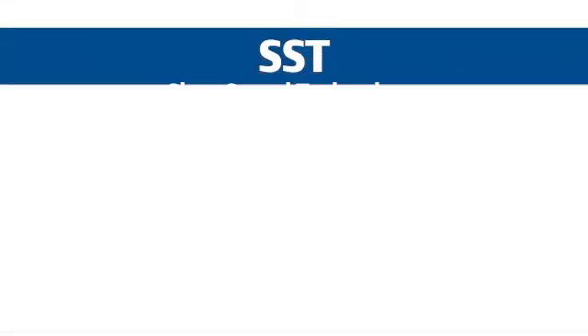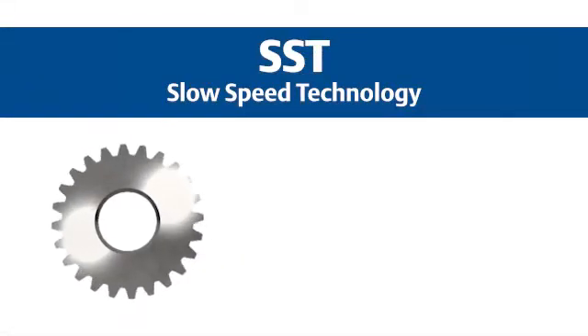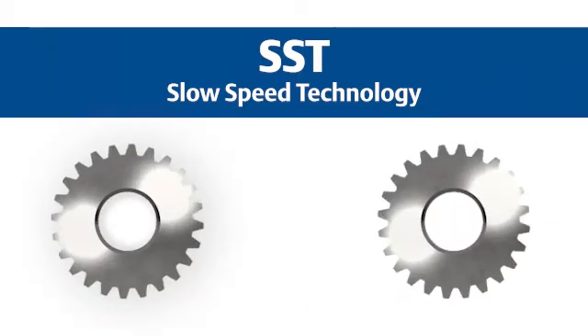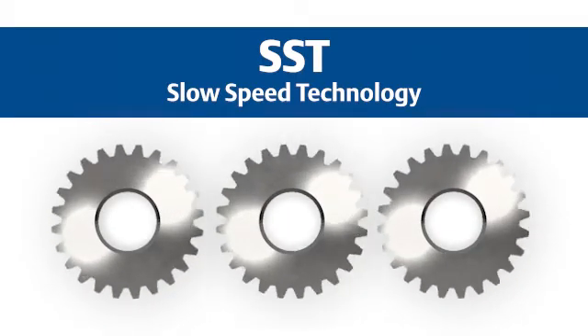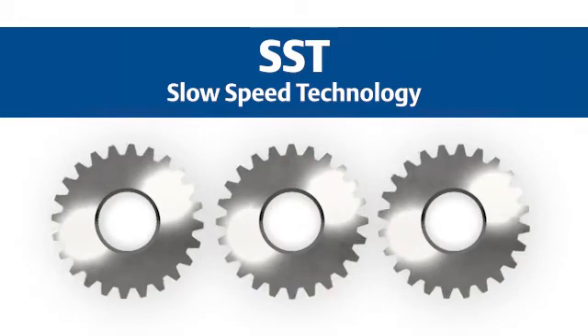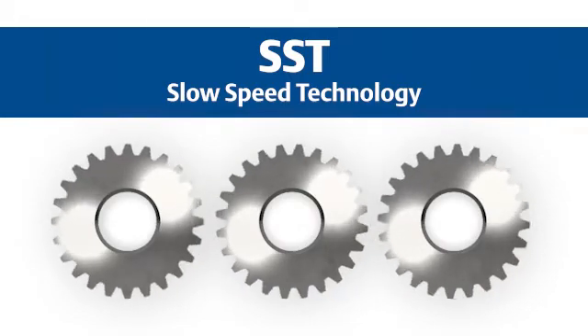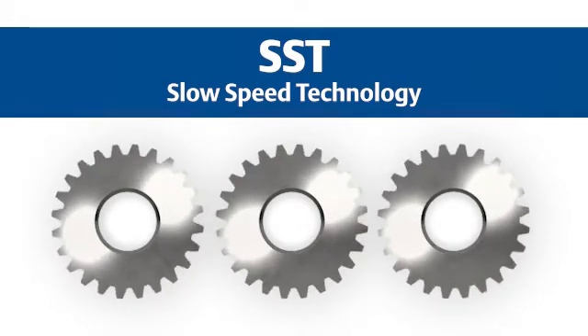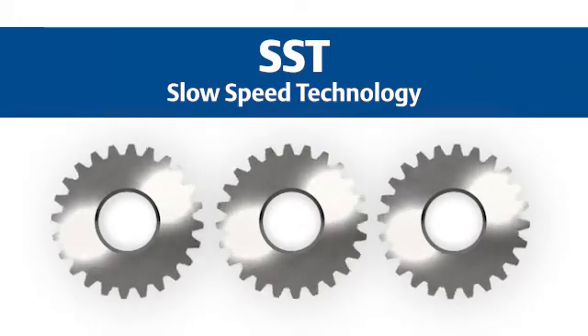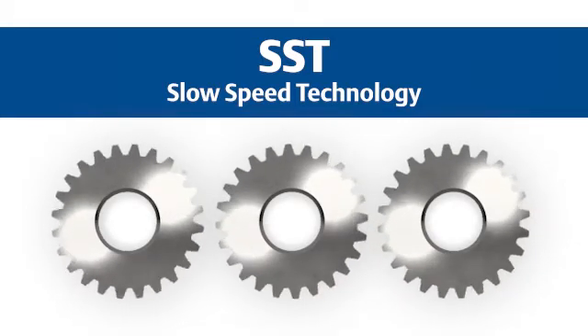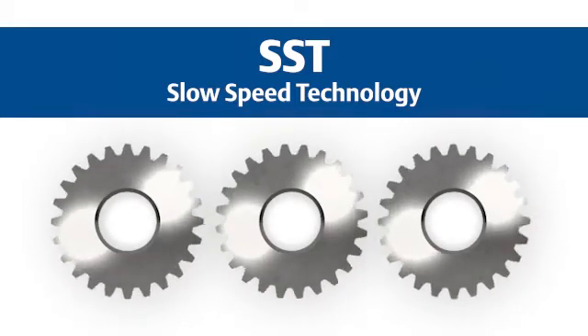Low-frequency analysis is sometimes referred to as SST or slow-speed technology. It applies to machines turning at very low speeds, typically below 10 Hz or 600 rpm. The SST process statistically enhances data to remove integration errors.